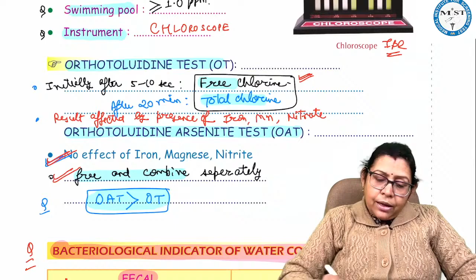Okay? So, the orthotoluidine arsenite test is better than the orthotoluidine because it tells us the free and combined chlorine separately, and there is no effect on the result if salts like iron or manganese are present. But in the orthotoluidine test, if these minerals are present, then the result will be affected, and initially it will show color change within 5 to 10 seconds. That is giving the free chlorine. But if you cannot note the color change within 5 to 10 seconds, then after 20 minutes you will be getting the total chlorine.